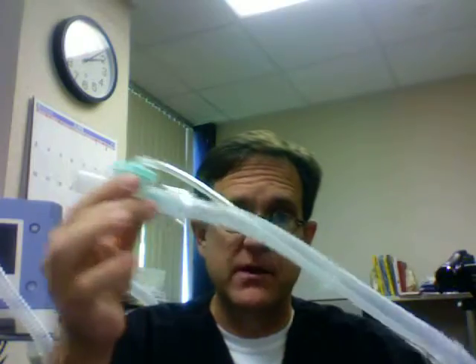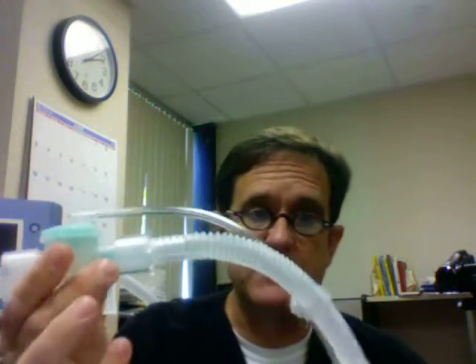Before I move on with that, I want to quickly show you an example of the active circuit. I had the passive circuit. This happens to be a pediatric active circuit. It has the exhalation valve on it. For those applications where you're in a volume or pressure control ventilation and the machine is not managing the leak very well so that you're getting an accurate reading, you could make the transition over to this active circuit.